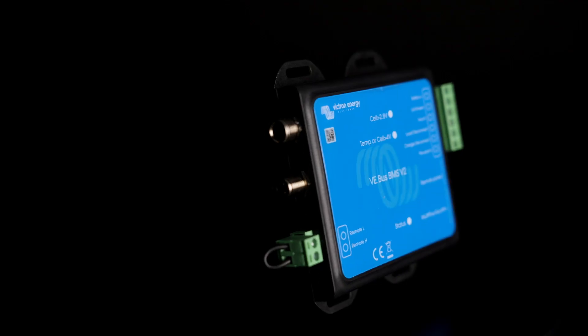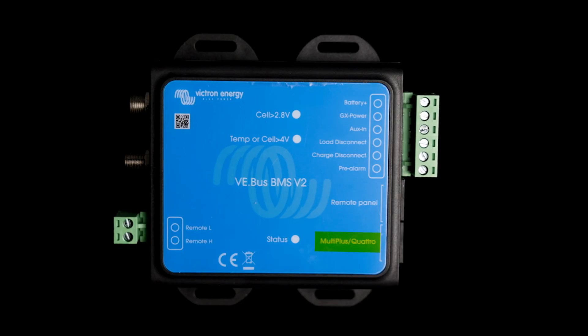Moving on from the Small BMS, we have the VE.Bus BMS, specifically version 2. With this you will get a VE.Bus mains detector, which is really important for use with the first generation MultiPlus and Quattros. On the MultiPlus 2s and the newer models of the Quattros, you don't have to use the VE.Bus BMS mains detector — that's all built in. The VE.Bus BMS version 2 was specifically made to work with MultiPlus and Quattros, and you'll see on the front it actually says MultiPlus and Quattro for one of those VE.Bus ports.